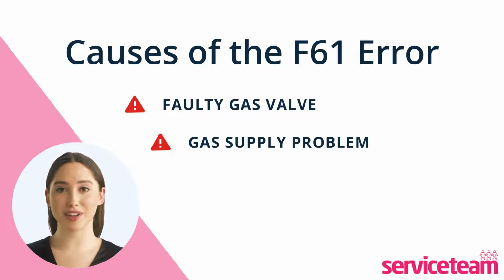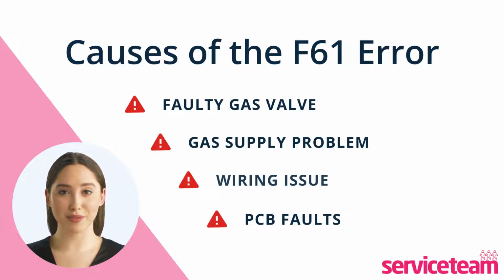The F61 error code can also be triggered by loose wiring between the PCB and gas valve or issues with the wiring harness. This can disrupt the boiler communication. The F61 error code can also appear due to a faulty PCB, whether it's due to component breakdown or communication glitches. It's important to get a gas-safe registered engineer to fix PCB issues immediately.